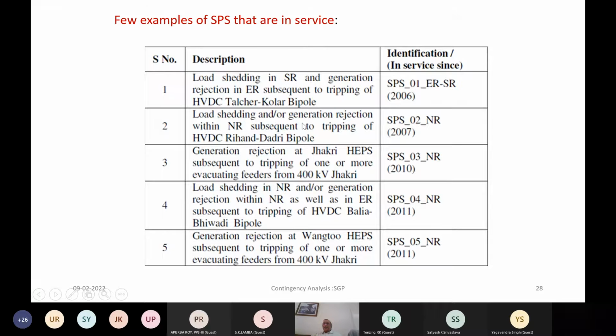Second scheme is load shedding or generation rejection within northern region, subsequent to tripping of the HVDC Rihand Dadri bipole. Again, a similar example. A major tie line has tripped or power flow got disrupted. So you are doing the load shedding in the northern region so that flow on the other balance lines which are remaining in service can be kept under control. Generation rejection at Jhakri hydroelectric power station subsequent to tripping of one or more evacuating feeders. These are the type of scheme which are very typical to hydro stations. Hydro stations typically rely on, say, 2 lines evacuating full power or 4 lines evacuating full power, and tripping of one or more lines results in overloading of the balance lines. So special protection scheme at hydropower stations is also one of the common features.